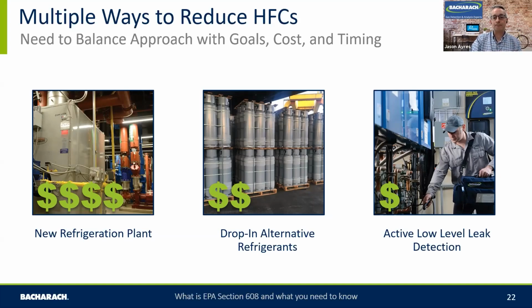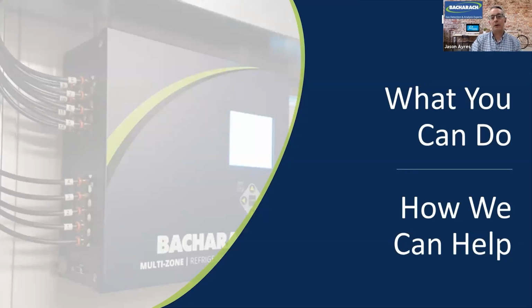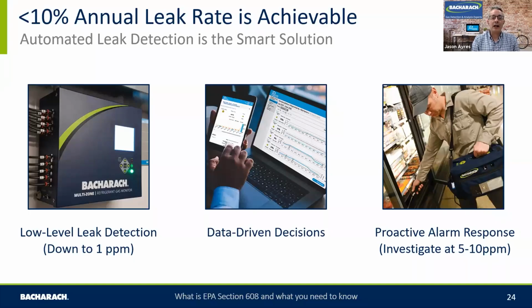So how can Bacharach help with this approach to refrigerant management and refrigerant reduction? Well, if you want to have a fully connected solution and look at being a leader in sustainability, with a very achievable leak rate of under 10%, you can do that. And it forms under 3 areas. First of all, it's having the right type of technology out there, the right type of leak detection that can detect down to the 1 ppm level, and that equipment deployed correctly within your estate. That will give you the foundations to detect refrigerant sooner.